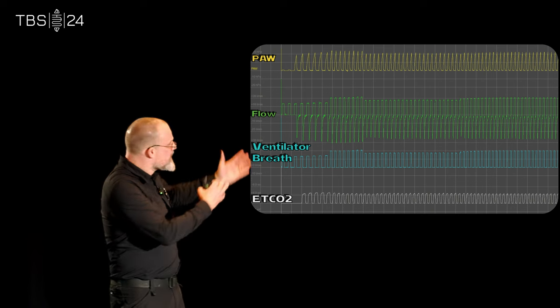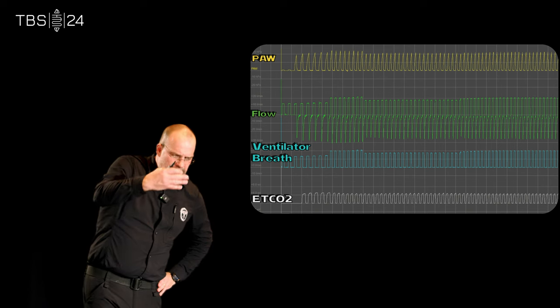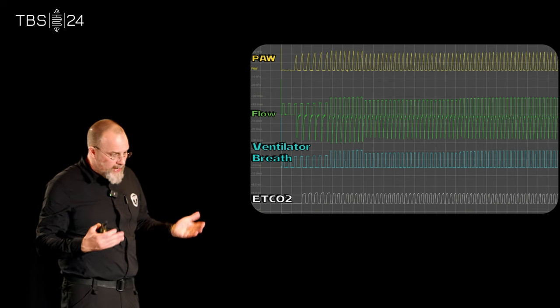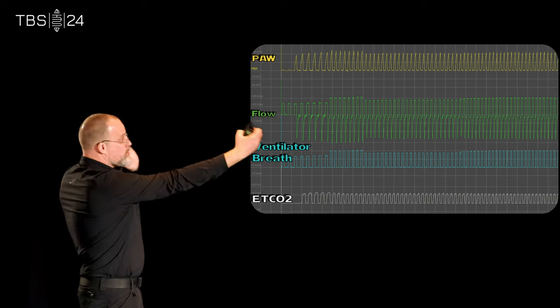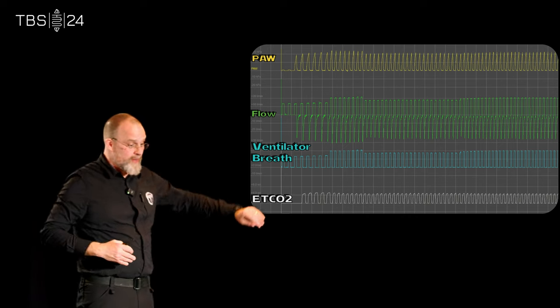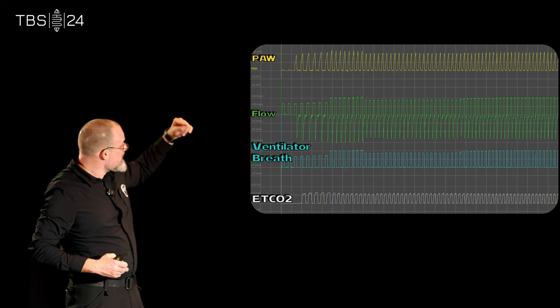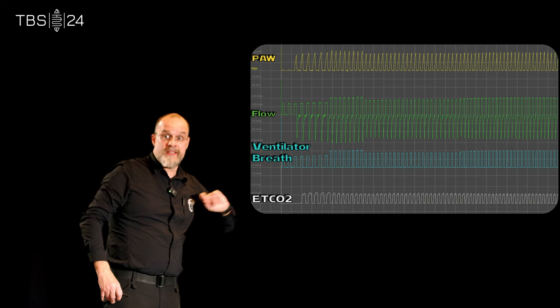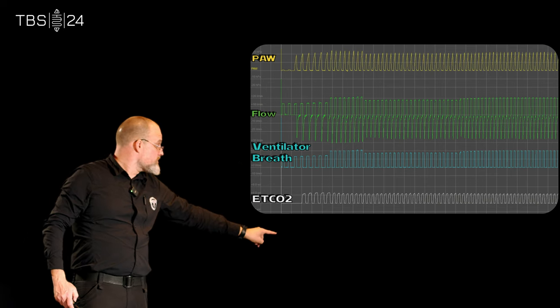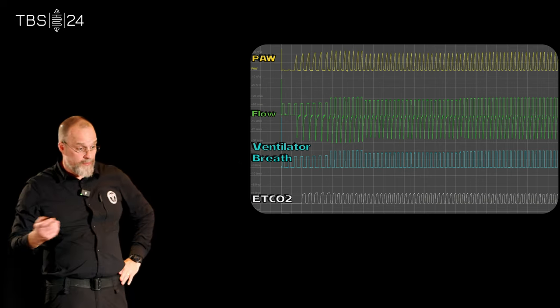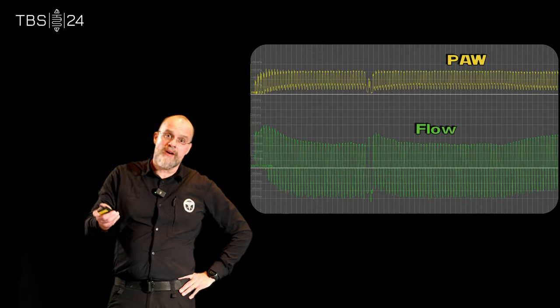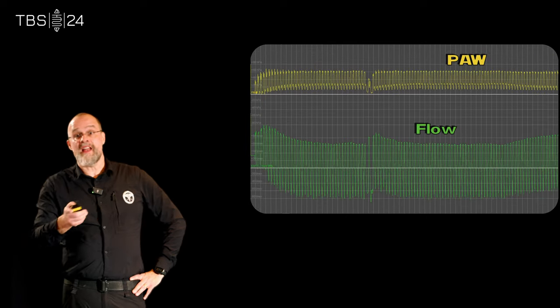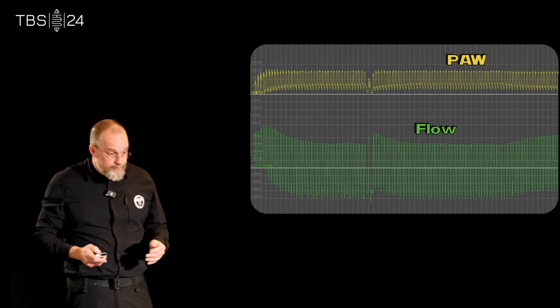So this is the sort of typical beat-to-beat or breath-to-breath data that we're able to retrospectively download. To put you in perspective, that's 30 seconds of fully automated CPR on that page - peak air pressures, flow, that 205 millisecond breath with the downstroke, and that's the CO2 produced from the patient. This is what synchronized chest compressions and ventilation looks like graphically.